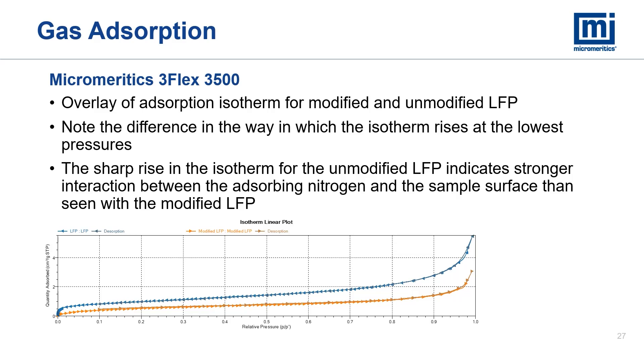For the modified material, there is not an initial strong reaction with the surface; rather, the amount of gas adsorbed becomes enhanced as more gas is adsorbed. For the unmodified material, the attraction between the sample surface and the adsorbing gas molecules is stronger than that between two adsorbing molecules. Whereas for the modified material, that attraction between sample surface and adsorbing gas molecules is not so much greater than that between adjacent gas molecules. This difference between adsorption force and condensation force is what drives the C value from the BET method, and here we see it graphically in the overlay of the adsorption isotherms.